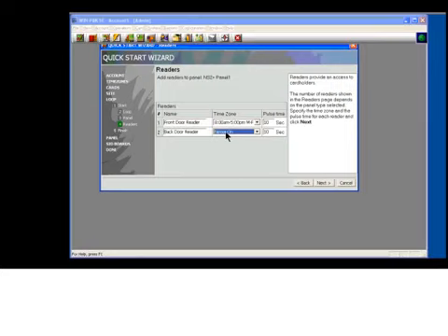Later on in the software, when we start manually unlocking and locking doors, you'll see that you have an option to restore to time zones. If you're using the word none, none's nothing. It's not a time zone. So you cannot restore to time zone. Where if you're using the word never on, it is a time zone, even though there's nothing in it. So when I click on restore to time zone, if never on is there, it'll put the door back to a locked state.